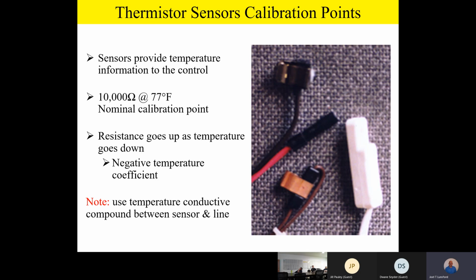So that's, again, a negative coefficient thermistor, but they all have that same calibration point at 10,000 ohms at 77 degrees. And those can be tested very, very easily with a cup of water that you know is 77 degrees. Put some saran wrap on there so you don't soak that sensor and the wires in water, and stick that sensor in there. You've got to read 10,000 ohms. Any questions or comments on the sensors and where they plug into the board, or any questions about that before we move on?